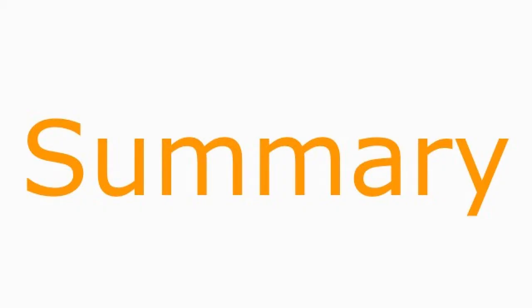Okay, so let's just summarize. We've installed our device, we've connected all the cables, and now we've triggered the sensors and checked that everything's updating in SmartThings. We've also connected our siren and internal sounder, and we've tested that the strobe, the siren, and the internal sounder are operating correctly. We've switched them on, we've switched them off. We know that everything works correctly.